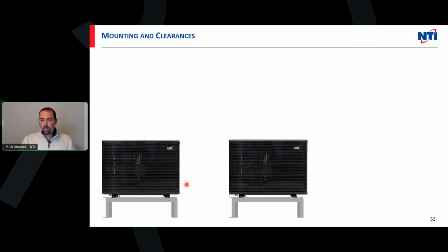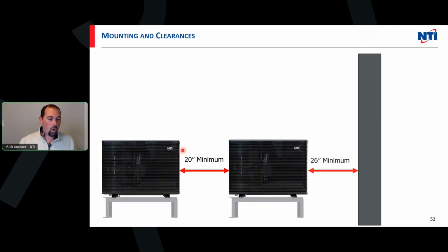So we do have some clearances for being able to work on these machines, as well as for having proper airflow. 20 inches minimum when we have two units together. This way we can get inside. On the right-hand side here, there's a panel that comes off. It's also where the pipes are. The electrical comes in, so if there's anything that needs to be touched, the electrical inputs are here as well. So we want to have some room for serviceability. If we are putting them against the wall, try to have about 26 inches minimum.